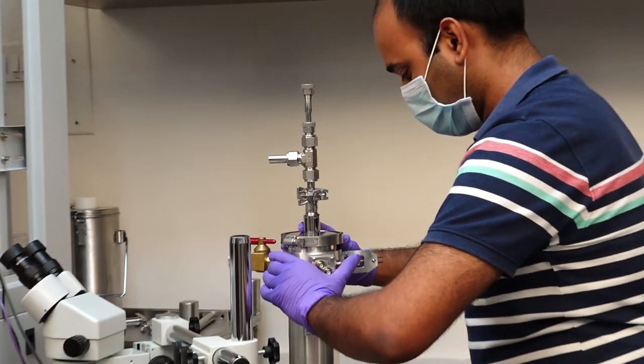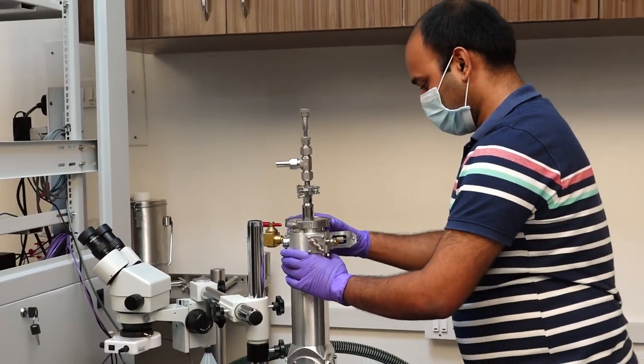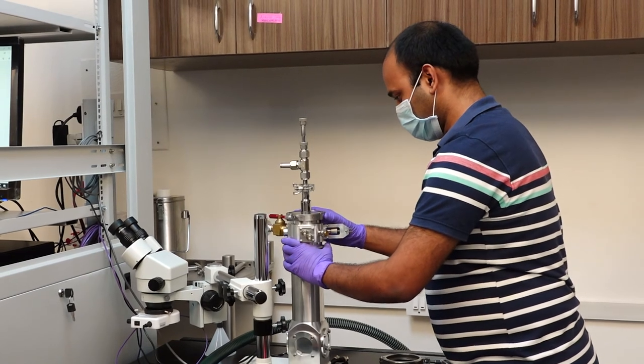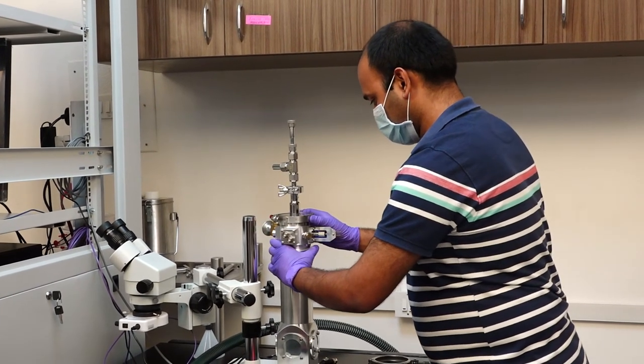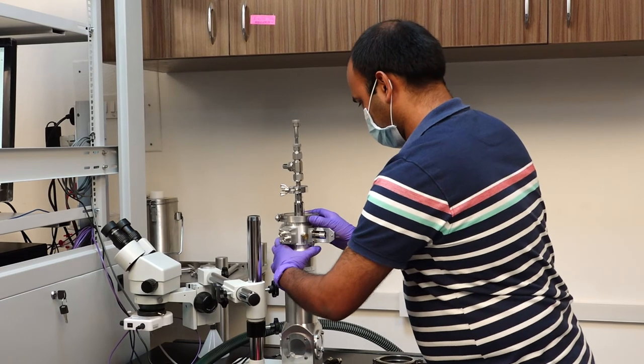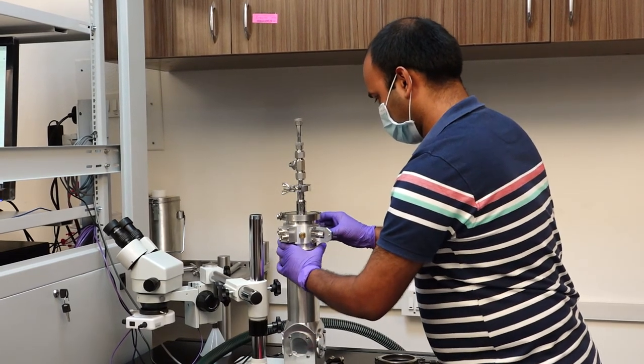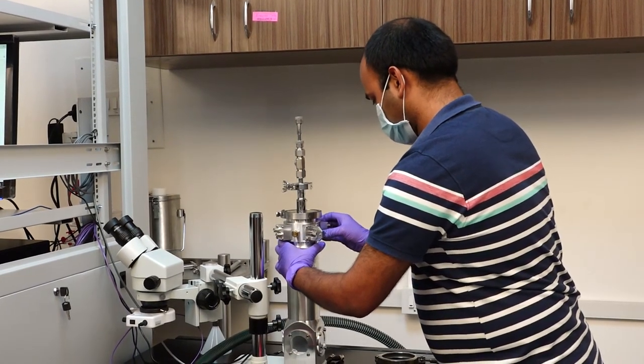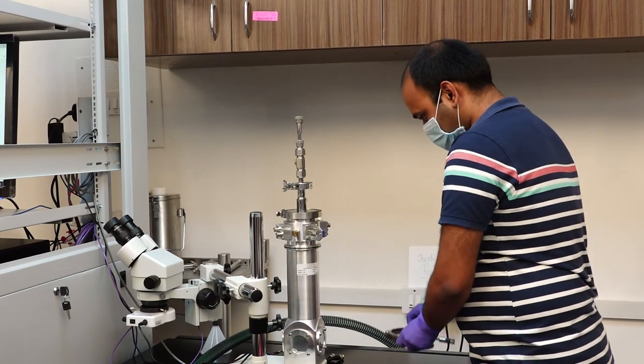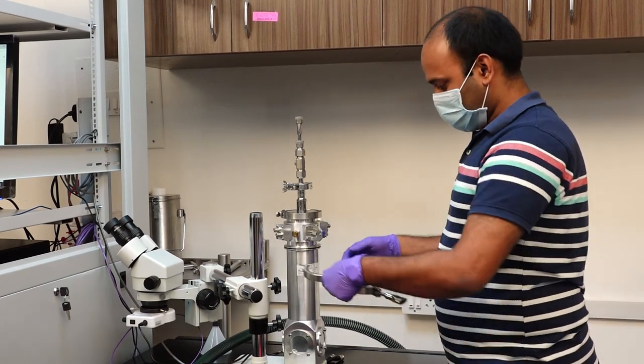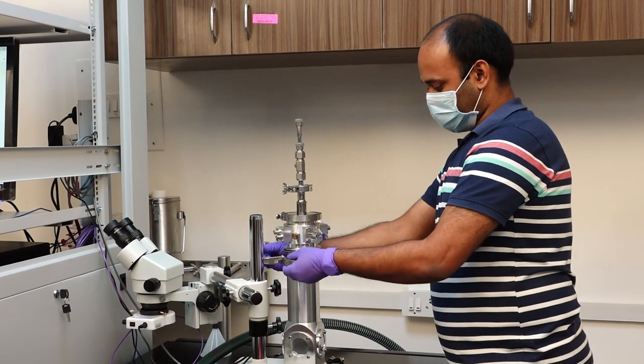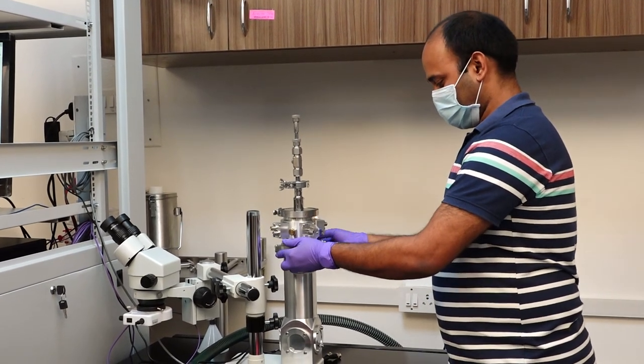So we safely land this stage into the O-ring, and then we change its orientation so that we can connect the turbo pump to achieve millitorr range pressure. These accessories are for maintaining vacuum. This is the KF flange which is being connected.